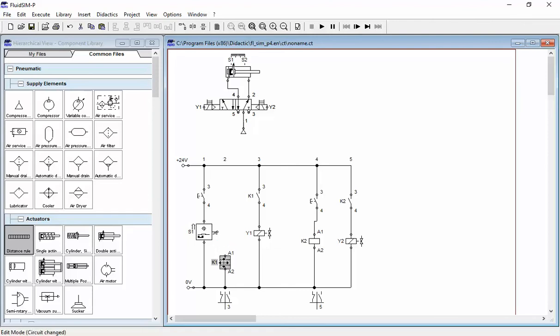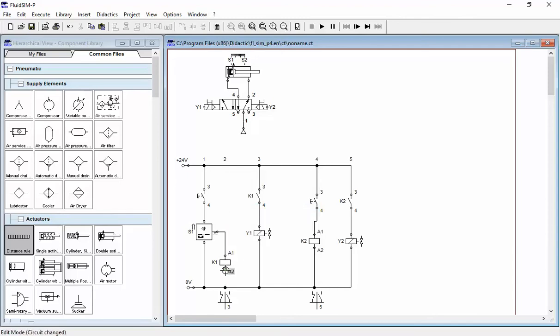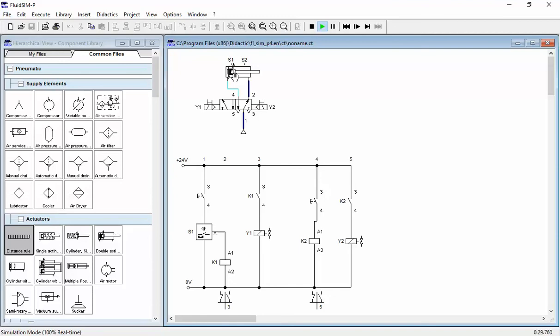Once the cylinder is in the backstroke, S1 will be under the magnetic field which is inside the piston of the cylinder. In this case, if I click the push button, I will activate S1. I will give power to S1. So S1 will produce a signal to K1, and K1 will activate Y1, and the cylinder will move out by this way. Once cylinder moves forward, there's no signal because S1 cannot see the magnet anymore.